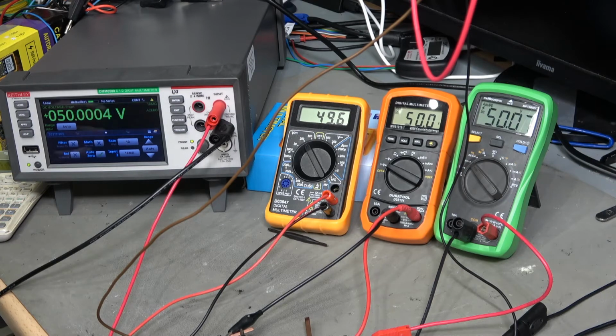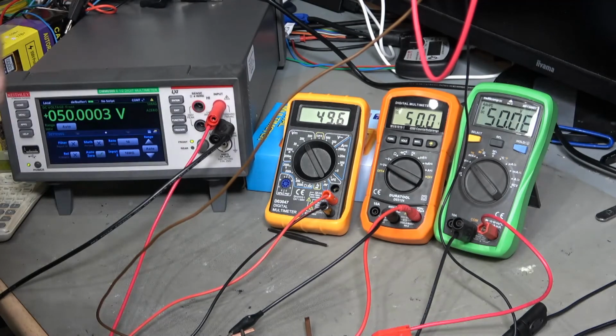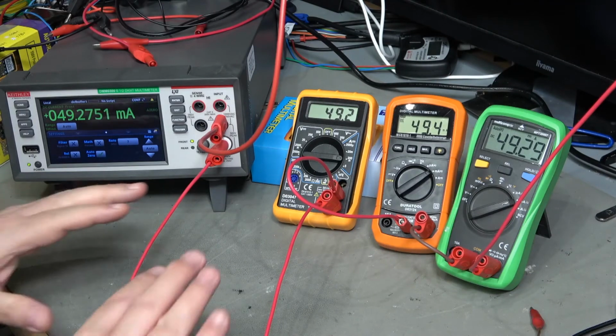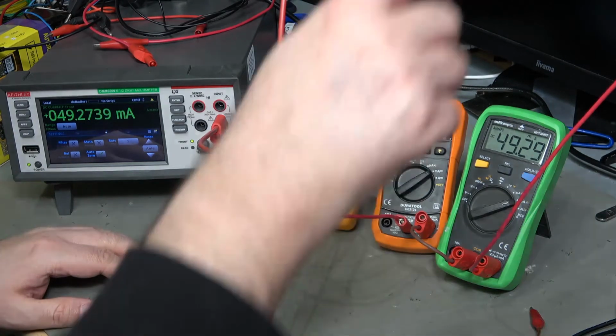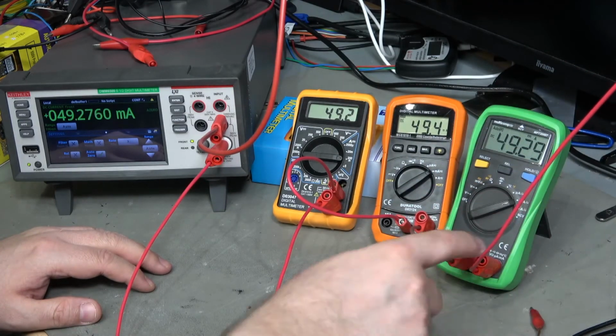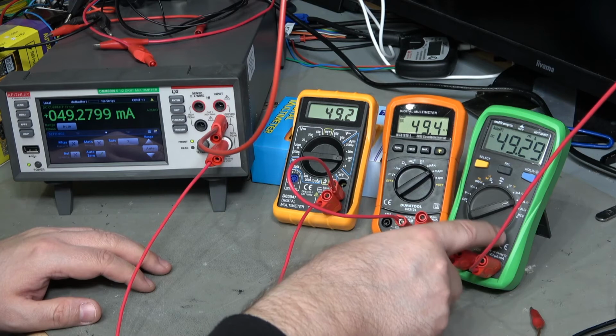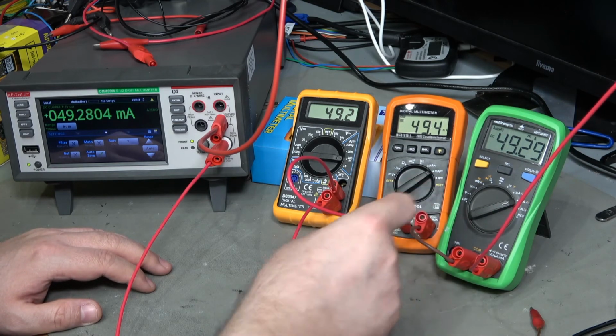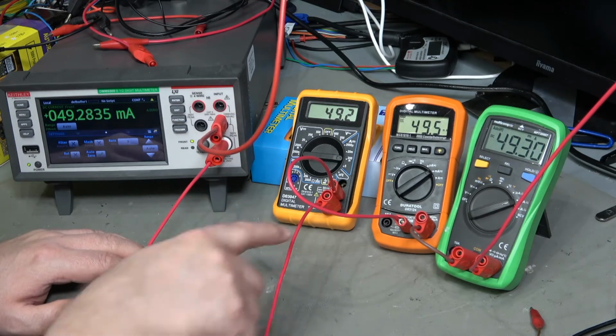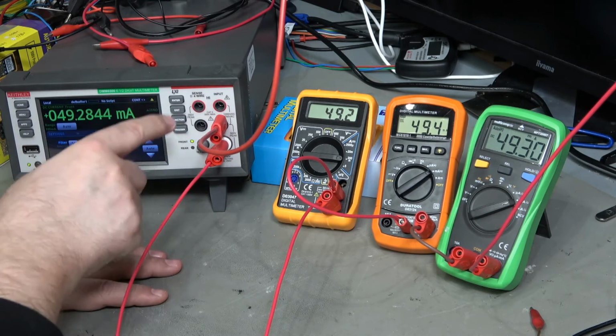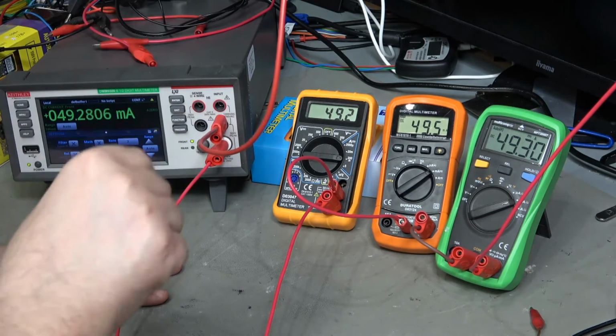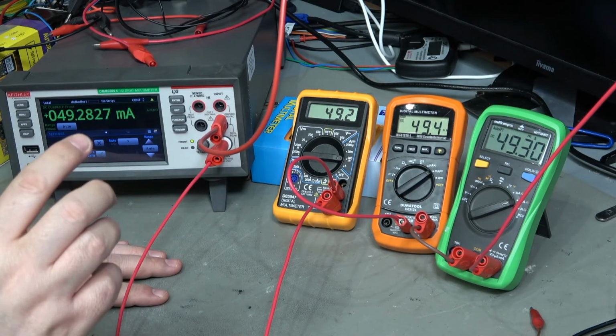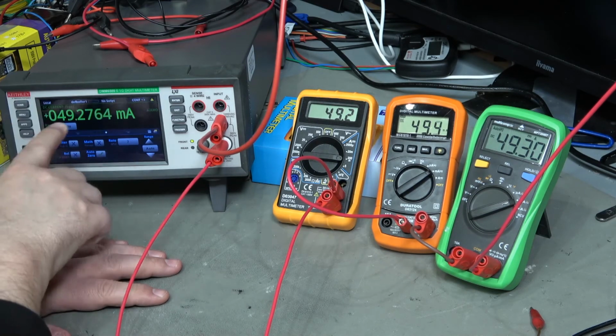What I am interested in, though, I've made a big point about ensuring that you get something with current measurement on it. So I'm going to set up some experiment now so that we can compare the current measuring capabilities of these. Okay, so I've got these set up for reading current now. Essentially the plus comes in here and goes into the milliamp input on this, comes out the common into the milliamp input on this one, out the common into the milliamp input on this one, out the common and into the milliamp input in this one, and then it comes out the common in here and goes up to the load, which is programmed to draw 50 milliamps, but it's actually drawing 49.2.